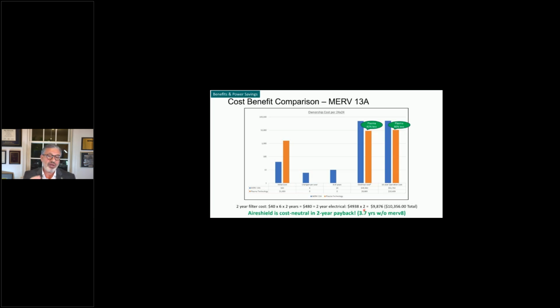So not only if you're using MERV 13s to control pathogens, and you should be looking at MERV 13A to control potential pathogens in the space, or if it's just to control ultrafines within the space, you can downgrade that down to a MERV 8 and still achieve the same type of condition. So there is a payback that can be taken into consideration.